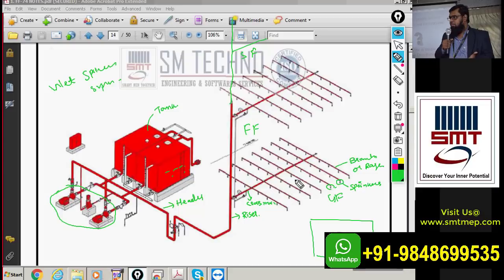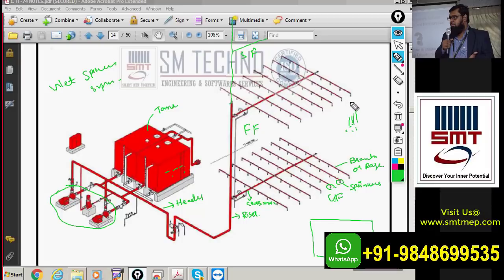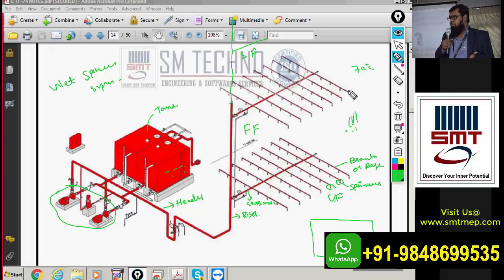In a wet sprinkler system, water is permanently charged in the complete pipe network up to all the sprinklers. In dry and pre-action systems the case is different. If fire occurs somewhere, because of heat the bulb inside the sprinkler contains a liquid that expands as per its thermal rating. The red color bulb has a thermal rating of 70 degrees centigrade. When temperature reaches 70°C, the liquid expands and breaks the bulb, allowing water to pass through the sprinkler.